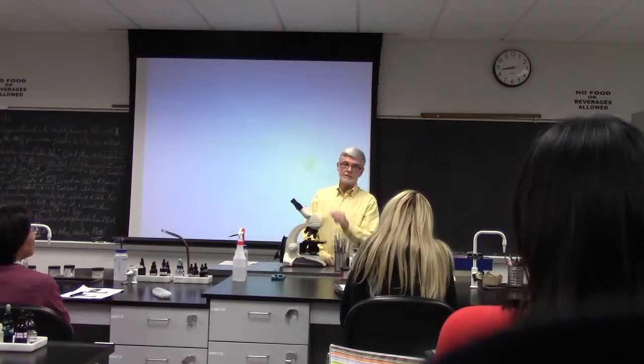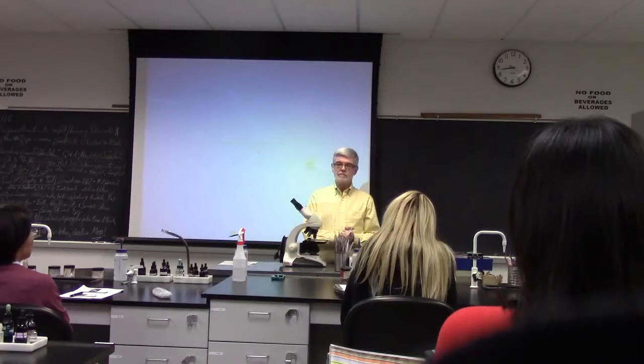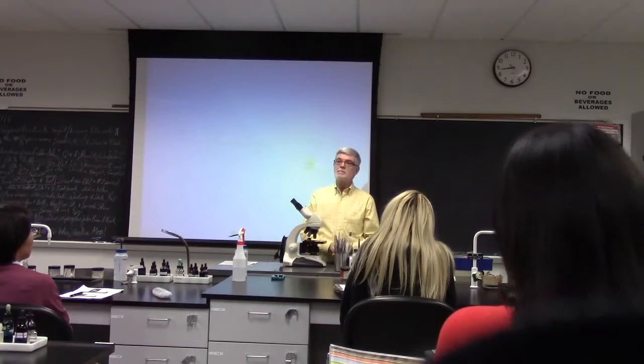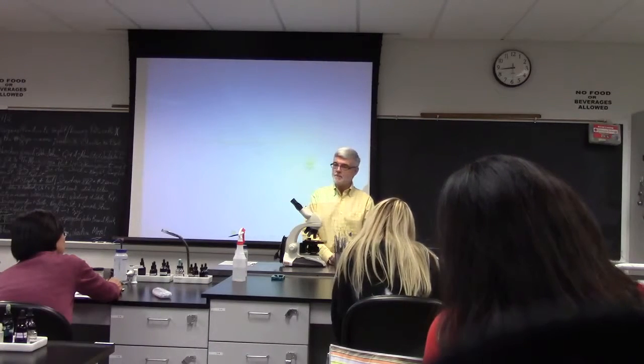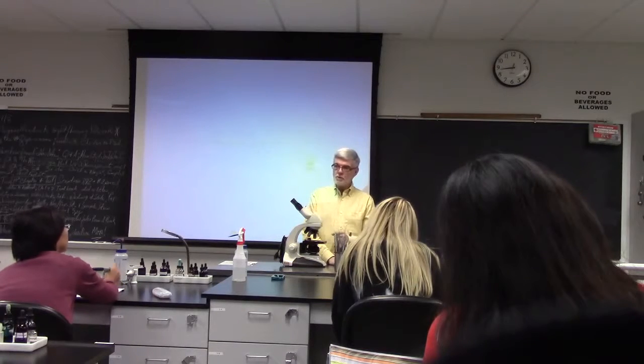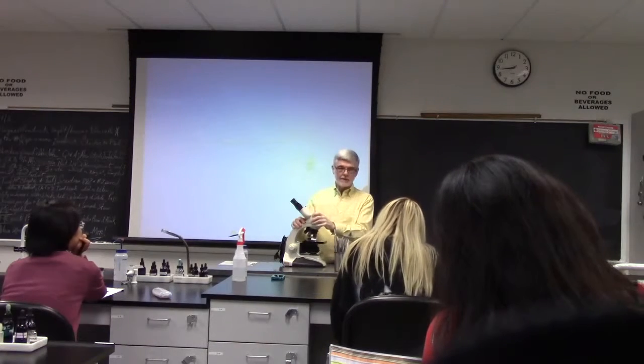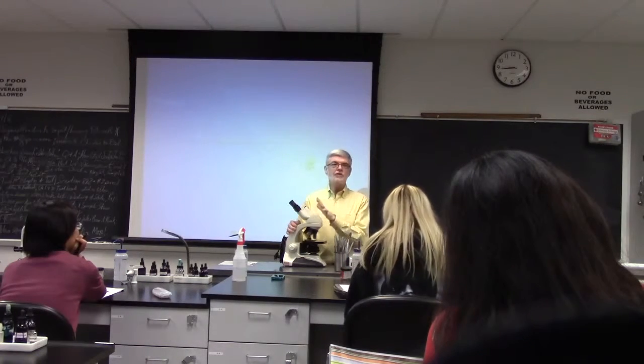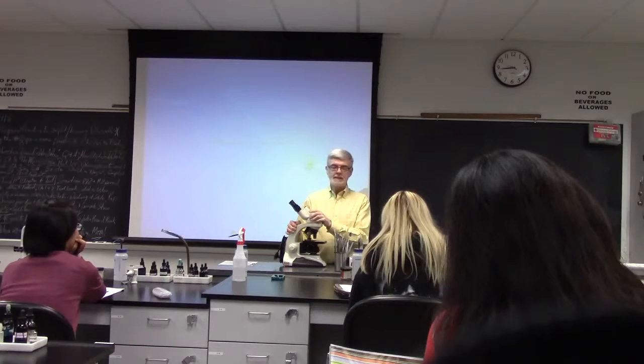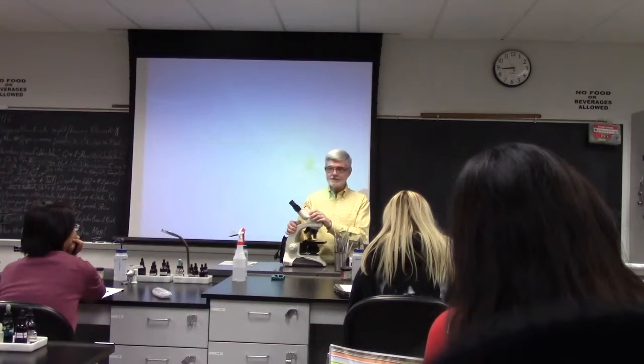A replacement oil objective costs around $1,400, and this whole microscope is $7,500. That's the big problem with all microscopes. What's the specific design fault with your particular microscope? This is the best microscope made — the Leica DME, used at USC Medical School, UCLA, Harvard. It's the best microscope money can buy, but it has a design fault. Remember the diaphragm that concentrates the beam? In every microscope you've ever used, it's a lever. Not in this one — it's a ring.